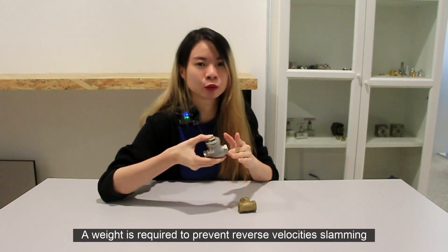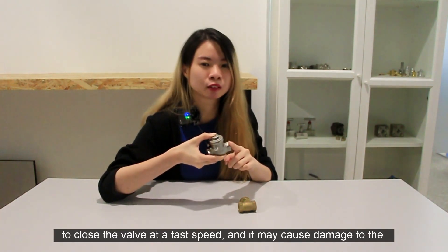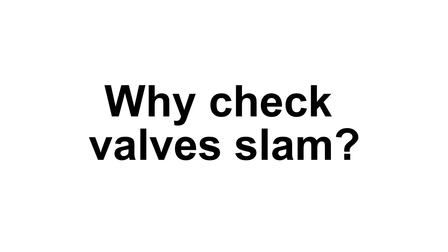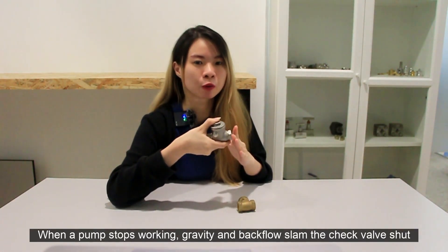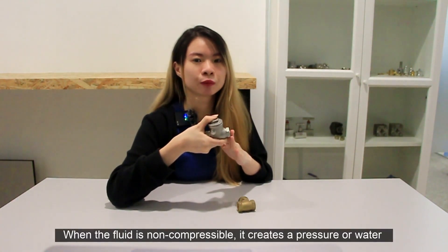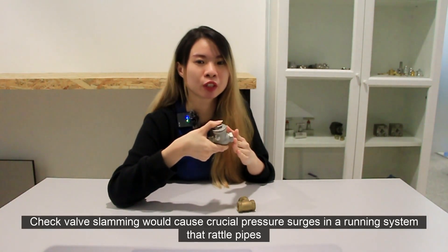A weight is required to prevent reverse flow velocities from slamming the disc into the valve seat. This is because gravity is insufficient to close the valve at a fast enough speed, and it may cause damage to the seat, seals, and the surrounding pipeline system. A check valve relies on gravity and the reverse flow to close properly. Check valve slamming frequently occurs during pump shutdown. When the pump stops working, gravity and the reverse flow slam the check valve shut. When the fluid is non-compressible, it creates a pressure or water hammer wave. The fluid continues to flow back and forth until friction losses cause the wave to dissolve. Check valve slamming can cause a critical pressure surge in a running system that can rupture pipes and damage other equipment.